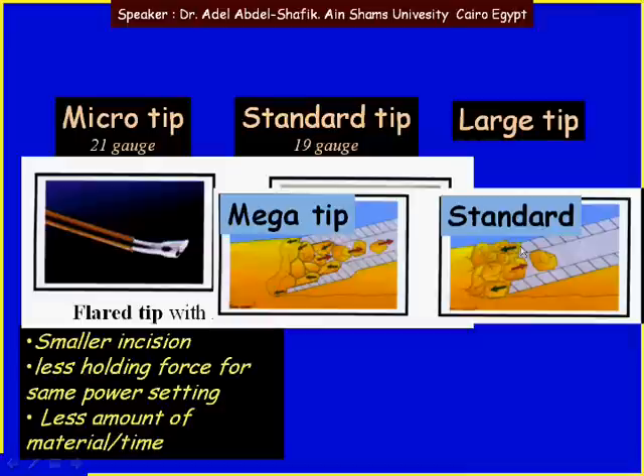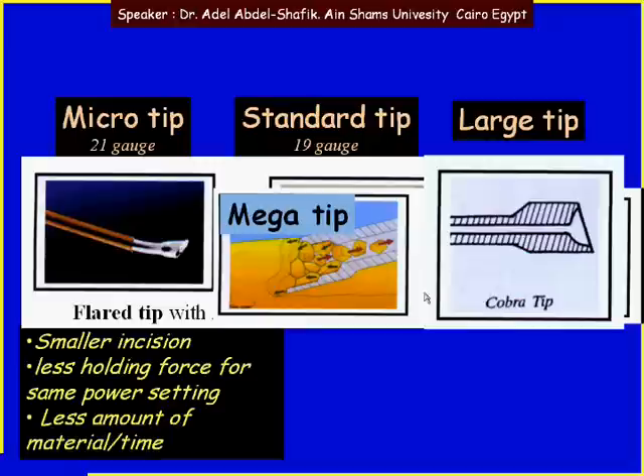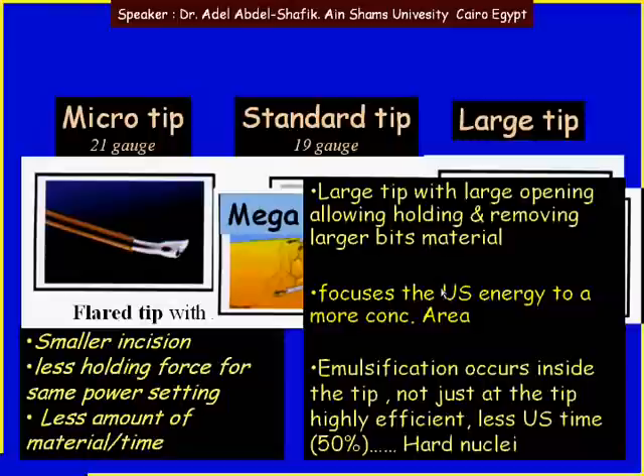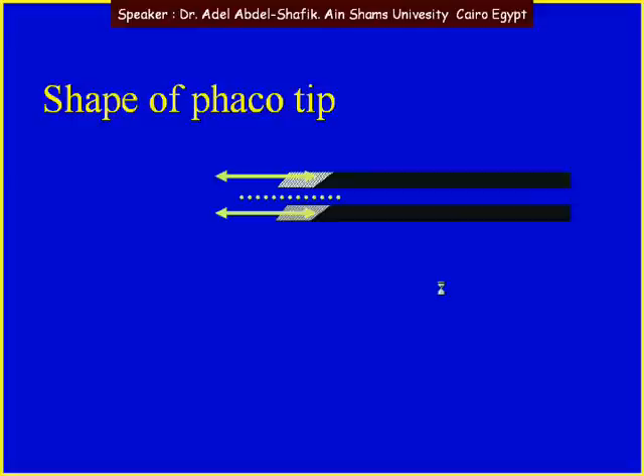We can also use a mega tip, which has a large opening at the end. The difference between the standard tip and the mega tip is that in the standard tip, the effect of fragmentation occurs opposite the metal part but not opposite the lumen. In the mega tip, we get a wide opening and a large surface area to get more effect. The same applies for the cobra tip. All these large tips focus the ultrasound energy into a more concentrated area, so emulsification occurs inside the tip, not just at the tip. This gives high efficiency and uses less ultrasound time, which is especially important for hard nuclei.